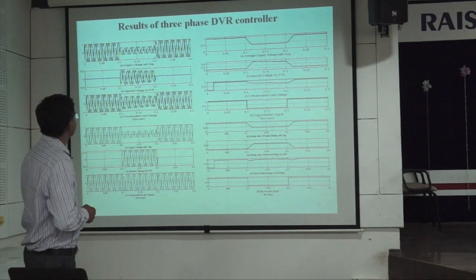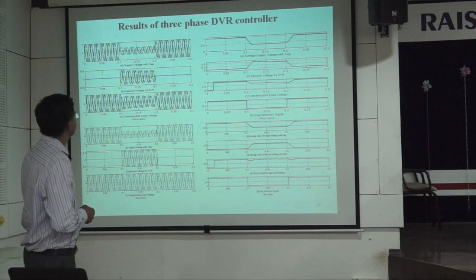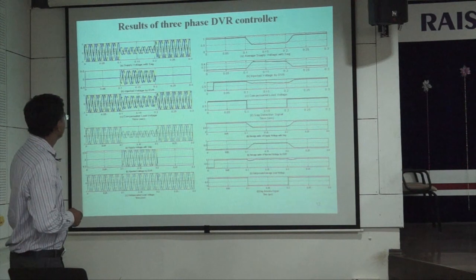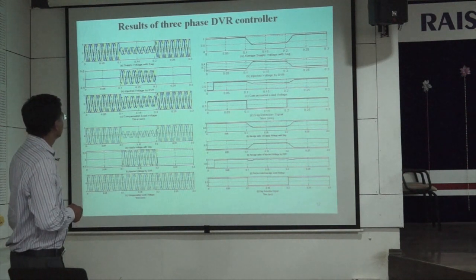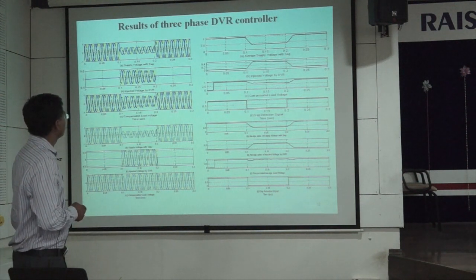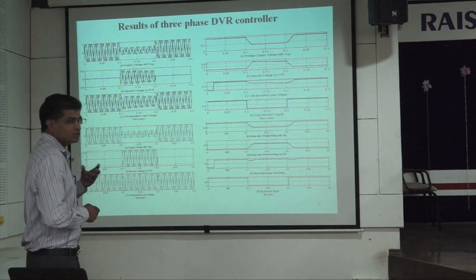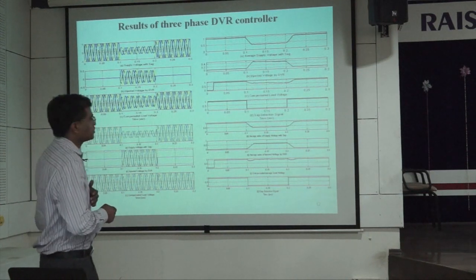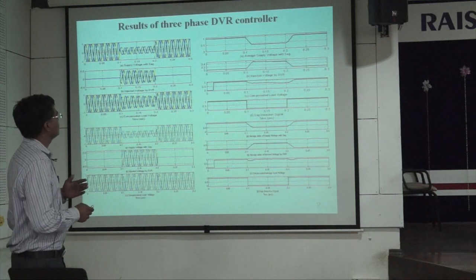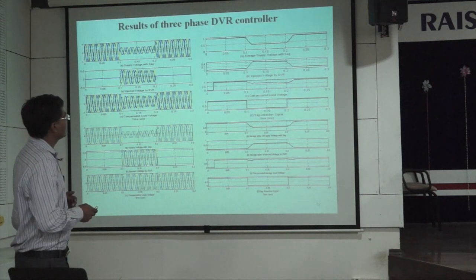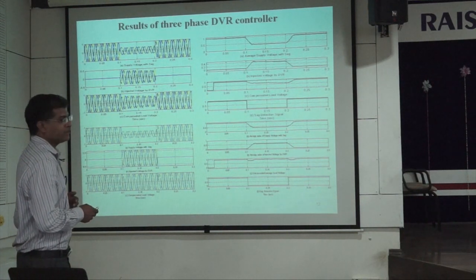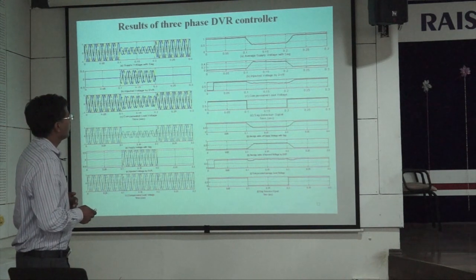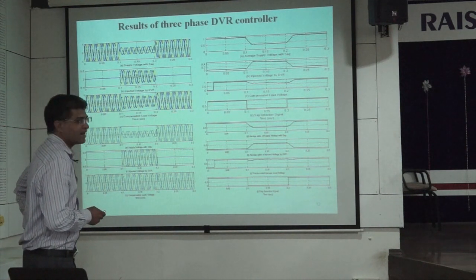So you can see from these results that it is not compensated truly. The load voltage is not completely compensated by this type of compensation, because the energy storage device has less energy. So due to that less energy, the average injected voltage goes on decreasing. That's why it is not compensated to the desired value.